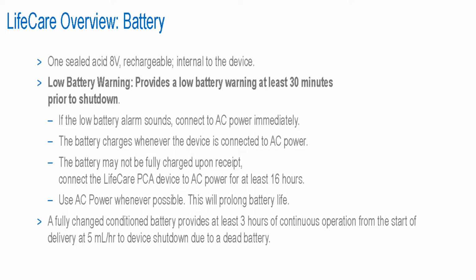With the Plum 360 pumps, it is important that they remain plugged in. A typical battery operating time with a new and fully charged battery is 4 to 7 hours, depending on the rate. If the low battery alarm sounds, connect the device to AC power immediately. The battery charges whenever it is connected to AC power. If the infuser is switched off, recharge takes approximately 8 hours.